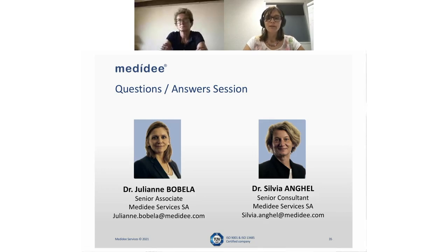At the current status, it is important as a sponsor to go and see what are the requirements of a given country. This should then be unified with time once EUDAMED is in place and where the registration is going to be more centralized. So I would say currently, yes, there might be a difference between countries, though they should currently already apply the IVDR requirements, but there might still be some slight differences. Afterwards, it's going to be centralized via EUDAMED, and then it should not make a difference anymore.